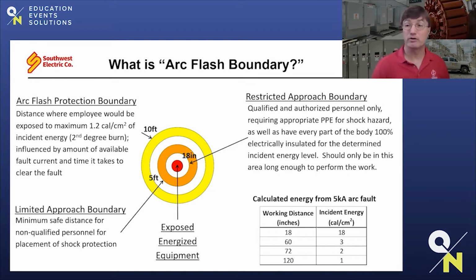Exposed meaning someone is actually working on that live equipment. The limited approach boundary requires a little bit more PPE. These are people who are trying to assist those who are working on the energized equipment, putting up blockades, putting up safety reminders, putting up shock blankets in order to contain energy should an event occur. And then the restricted approach boundary obviously is for the one who is working on the live equipment, and they're going to be the one who's most likely suited up like a fireman or a spaceman. You can tell on the table on the bottom right that the further away you are from the energized equipment that could experience an arc flash condition, the less energy you're going to feel, just like a campfire.